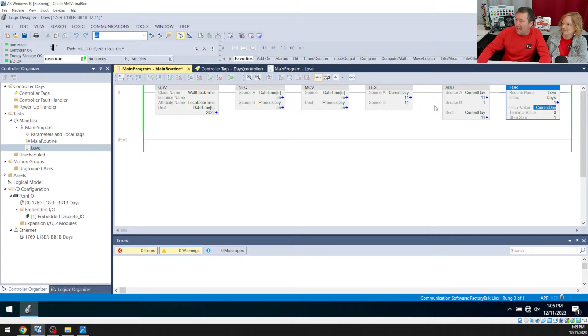So I'm going to right click controller tags, new tag, and we're going to make one called data. And I'm just going to make this a real, and I'm going to make it a dim 0 of 5. Now, the two ways you can do the dim 0. One, I can simply hit bracket 5 bracket, and that's a dim 0 of 5. But if you're not sure of that nomenclature, hit your dialog box here, which first of all, you could have scrolled up and down. You could have found the real. And down here, the dim 0 of 5. That's going to make an array that is a group of 5 points.